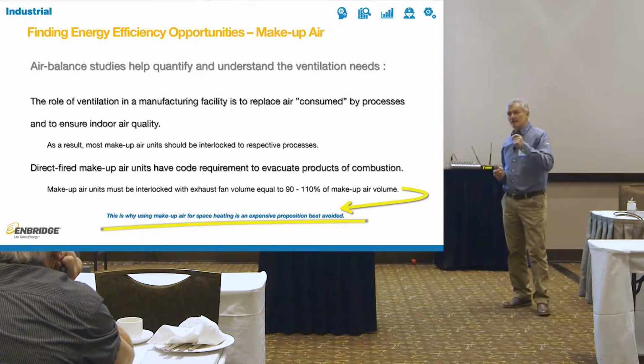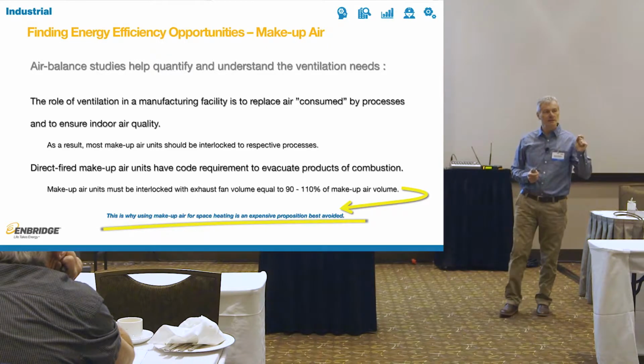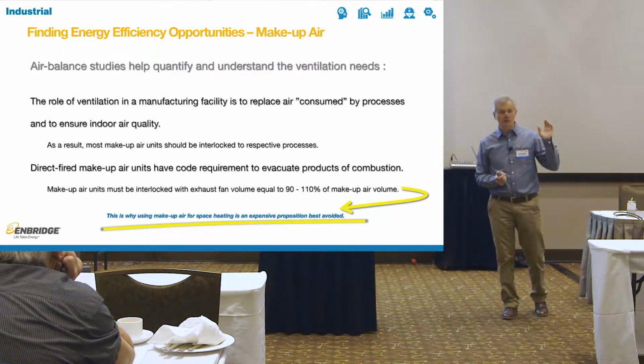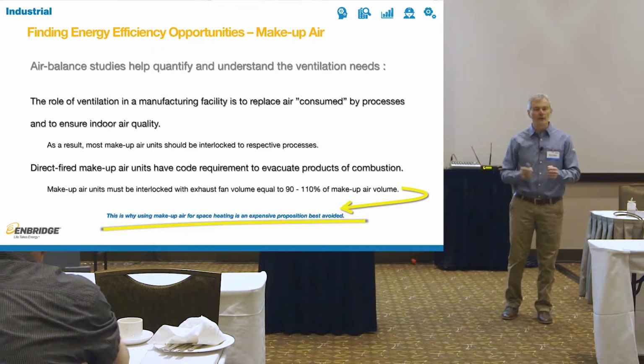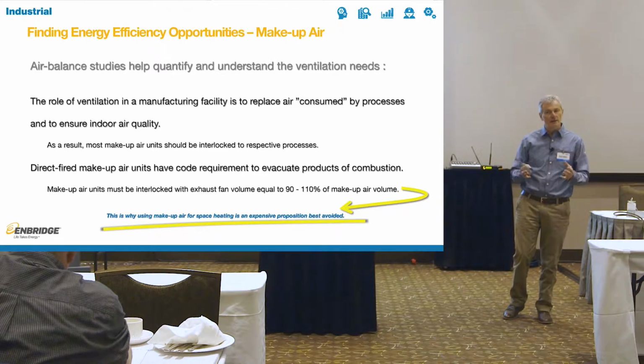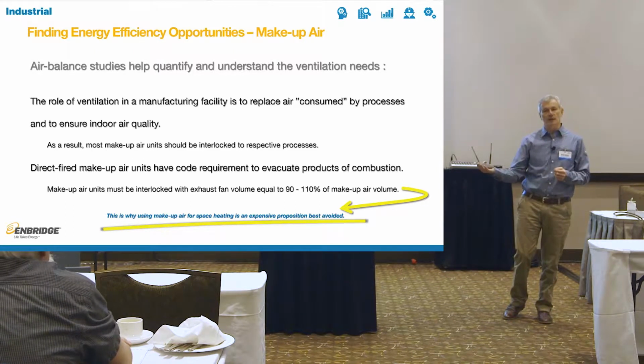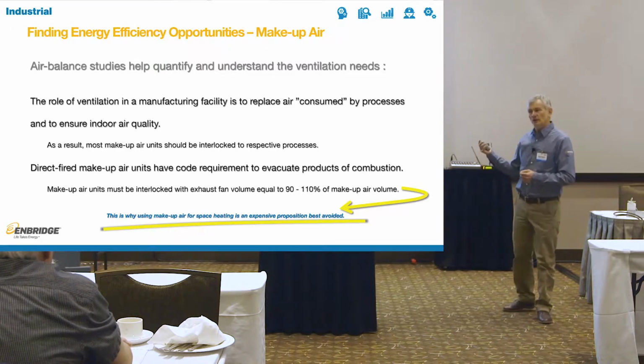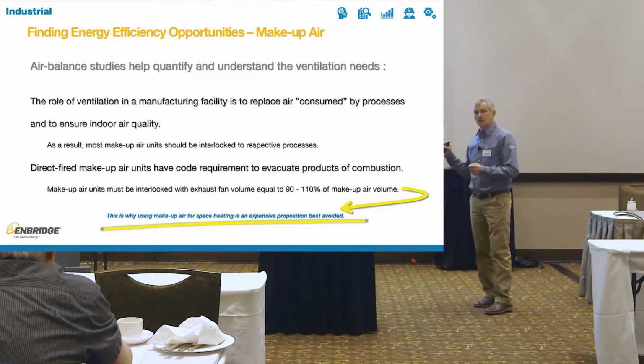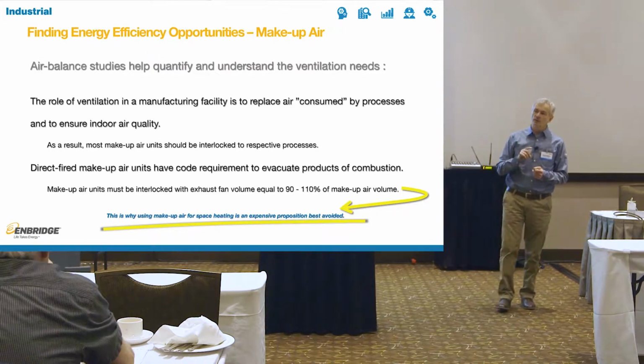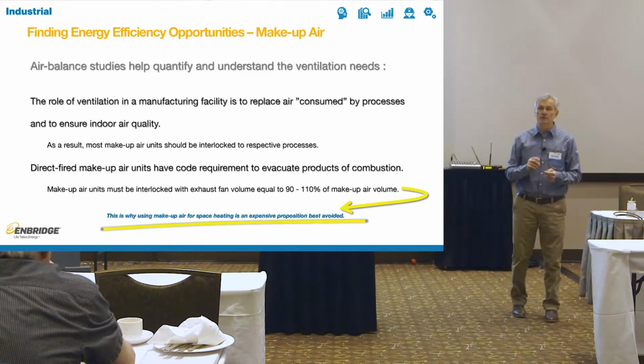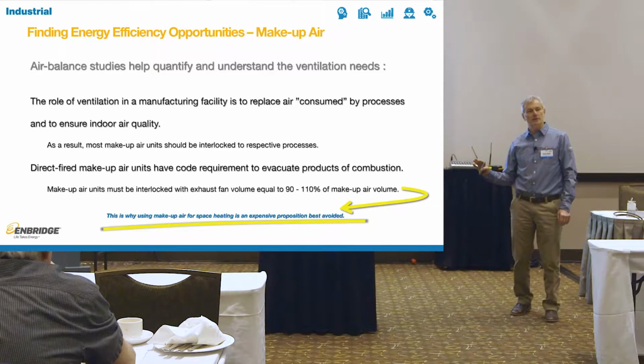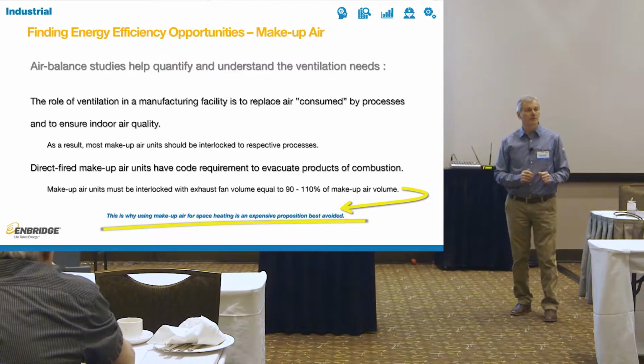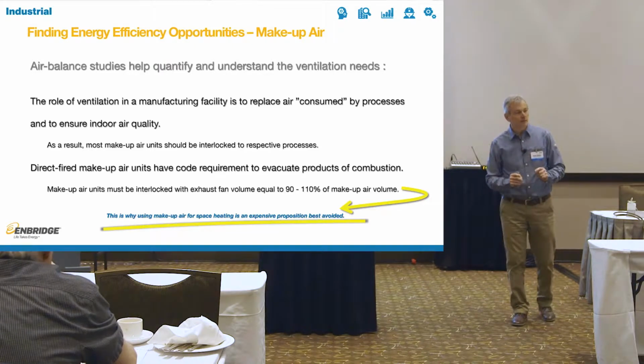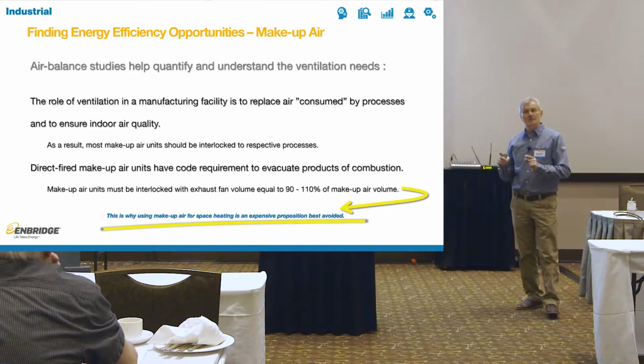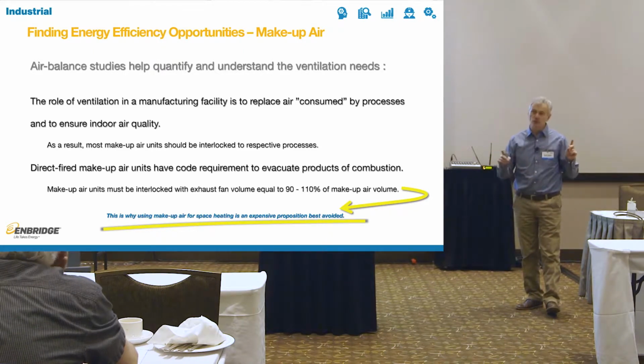And the reason is because there's processes going on. There's ovens that take up some of the air from the space, and they exhaust it out. There's some other, let's say, E-coat paint lines. There's other paint processes that require some air to be moved through it. As the air is moved through it, you have to make it up. So now, makeup air therefore is driven by the exhaust, and it should be usually interlocked with the processes. Very few people will have that. Very few people in your facilities will actually interlock makeup air with the process because everybody's afraid of poisoning their fellow human beings. But that's not what's going to happen. If there is no exhaust from the facility, there is no need to make up any air.